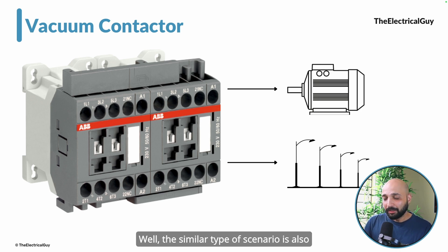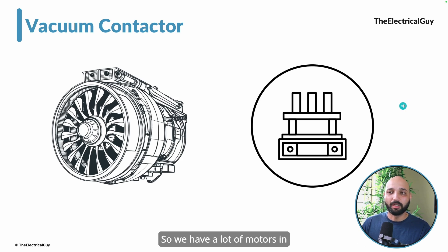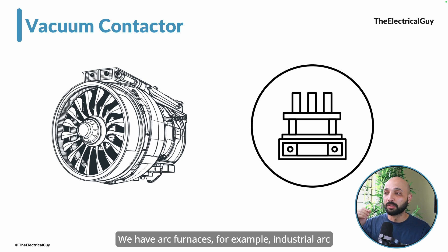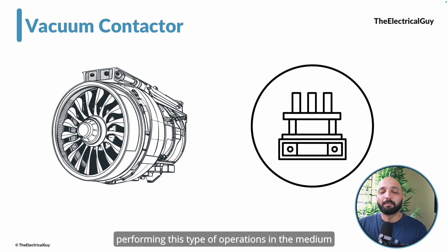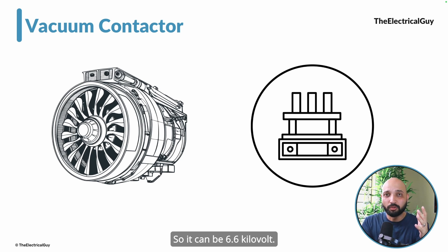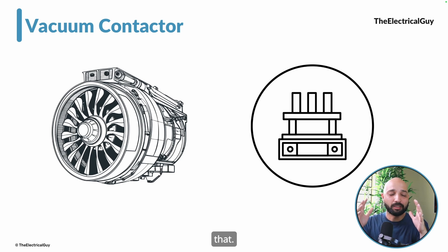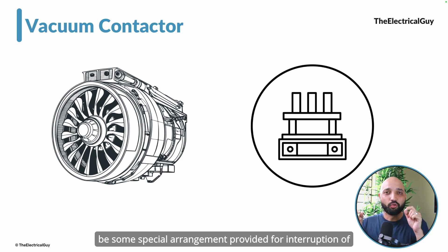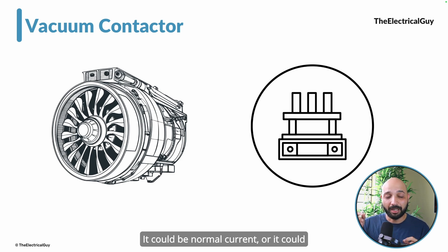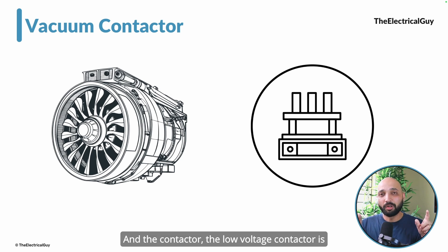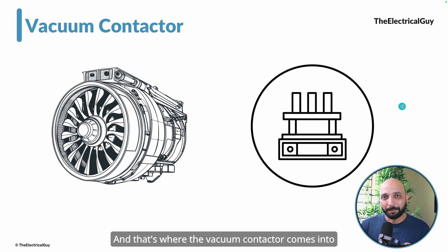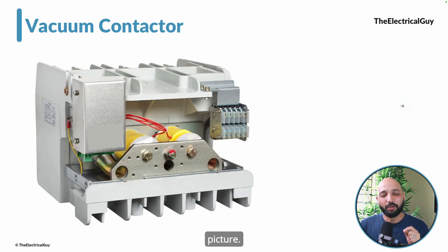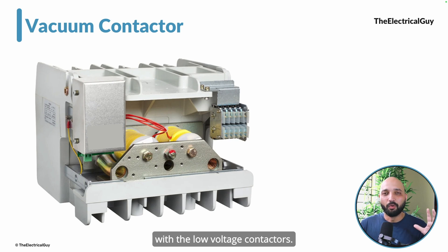A similar scenario exists in medium voltage systems — above 1000 volts. We have motors, arc furnaces, and other loads that need frequent switching. However, the low voltage contactor is not capable of handling medium voltage, which can be 6.6 kV or 12 kV. At higher voltages, a special arrangement is needed for current interruption. The low voltage contactor has no special interrupting medium, and that's where the vacuum contactor comes into picture.